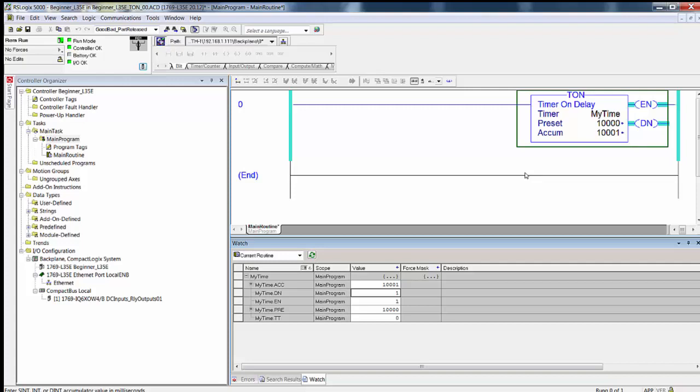The answer to that last question may vary, but normally if you clear the done bit directly from the keyboard or with logic, it will resume for possibly one scan and realize that it is done and set the done bit again. But you will not see the transition. The only reason you might realize that this happened is that the accum is now greater than the preset.